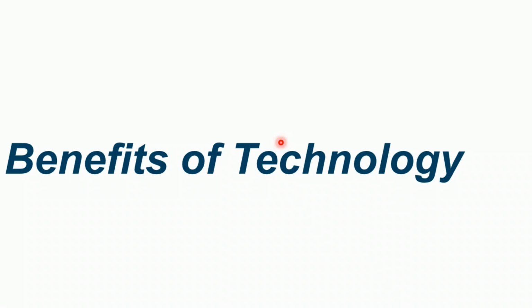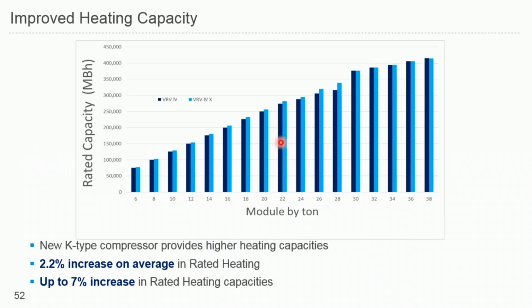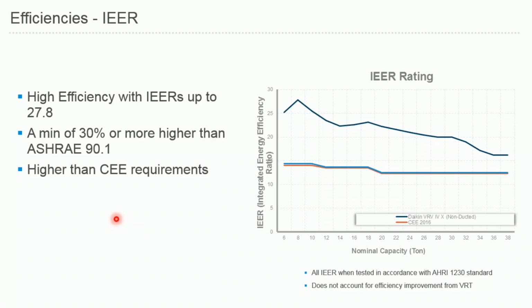So, the benefits of the technology, with all these new components, especially the addition of the K-type compressor, overall you're getting higher heating capacity. Your rated heating capacity will on average be increased by 2% compared to VRV4, and depending on the tonnage, the change will be different. You can get up to a 7% increase in your rated heating capacity. I believe that's the 28 or 24 ton model. From an efficiency standpoint, on IEER, your highest IEER will be 27.8. Overall, there is not much change on the efficiency side, but we're still way above the minimum ASHRAE and CEE requirements on the part load cooling efficiencies.